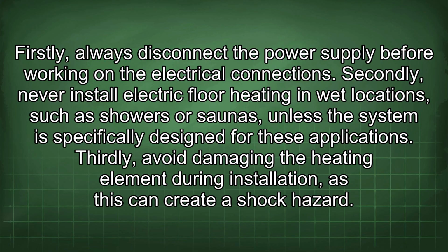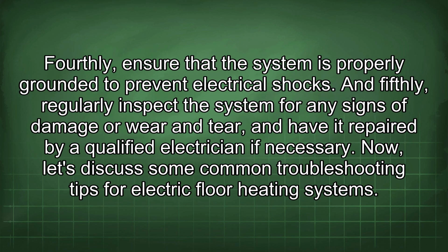Firstly, always disconnect the power supply before working on the electrical connections. Secondly, never install electric floor heating in wet locations such as showers or saunas unless the system is specifically designed for these applications. Thirdly, avoid damaging the heating element during installation, as this can create a shock hazard. Fourthly, ensure that the system is properly grounded to prevent electrical shocks. And fifthly, regularly inspect the system for any signs of damage or wear and tear, and have it repaired by a qualified electrician if necessary.